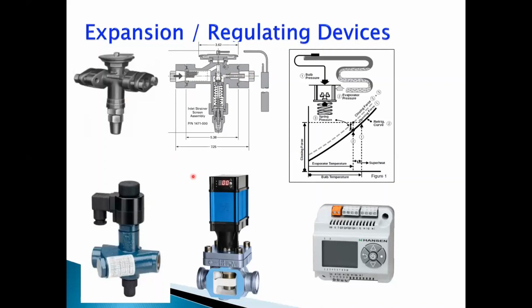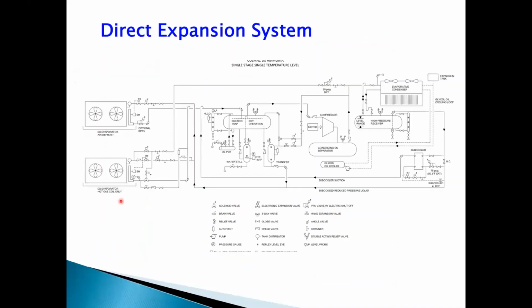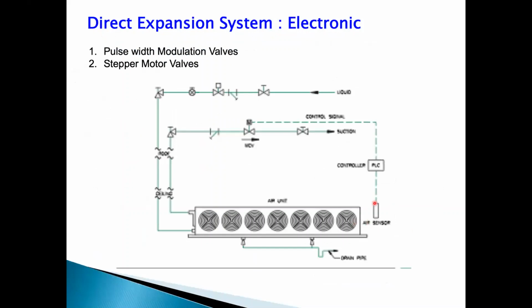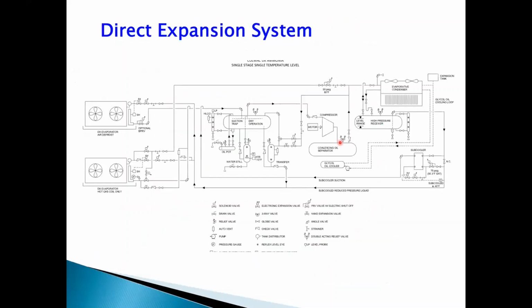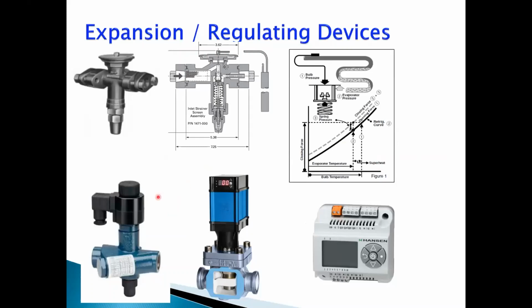As I told you, the evolution has come. Now we have these electronic expansion valves. Electronic expansion valves can be pulse width modulated valves or motorized valves. Pulse width modulated valve means that the on-off cycle of this valve is controlled by the temperature difference. If we see these sensors, normally sensors are used to sense the ambient temperature and the evaporating temperature of the refrigerant, and the electronic controller will sense the difference between the two temperatures and modulate the on-off cycle of this pulse width valve. Typically, it's designed from 1 second in 6 seconds to maybe 5 seconds in 6 seconds. Like that, it is on and off.